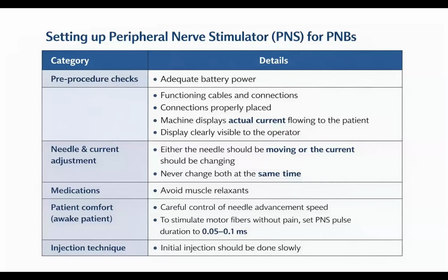And for setting up a peripheral nerve stimulator for peripheral nerve blockade, we need pre-procedure checks. Like we should check if there is adequate battery power and all the cables and connections are functioning, all the connections properly placed, the machine displaying actual current flowing through the patient, and the display clearly visible to the operator. And needle and current adjustments, like either the needle should be moving or the current should be changing, and we should never change both at the same time.